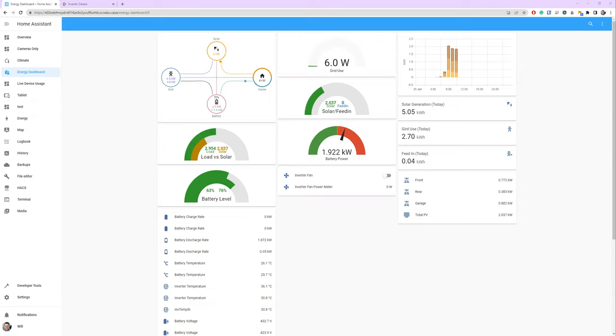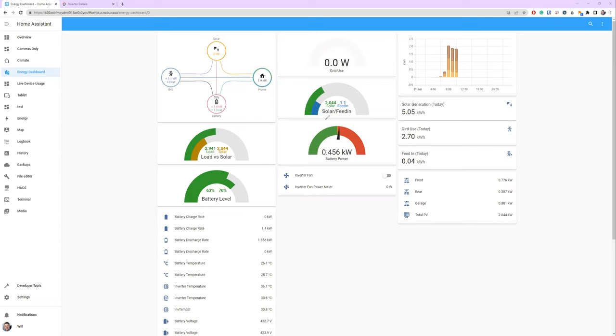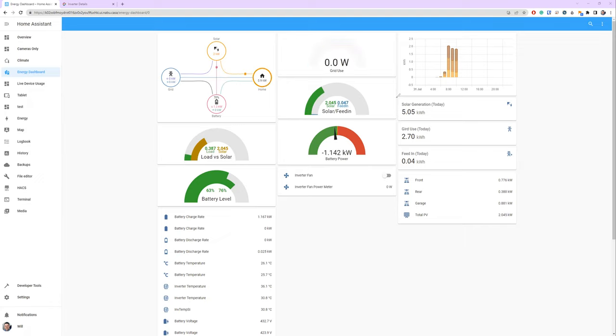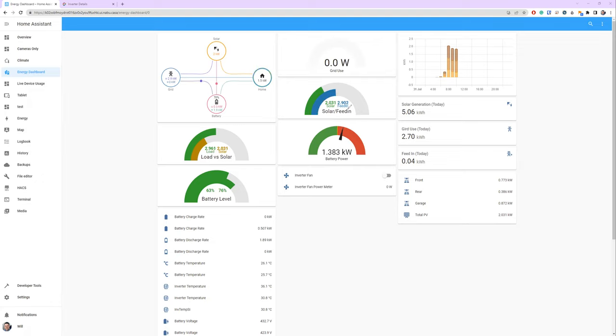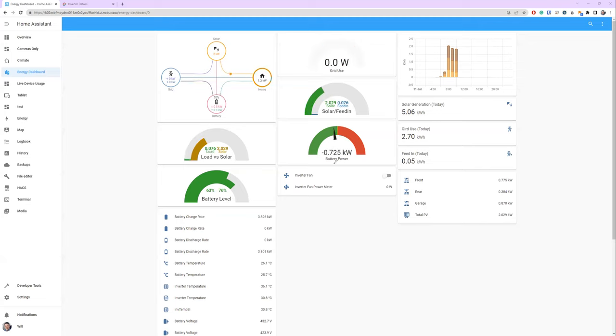So now we'll try turning the water heater off and we're going to watch in particular the feed-in amount here. So water heater is off. See, the feed-in jumps up and now the battery's responding. The grid has gone wild. This is the problem with any battery-connected hybrid inverter that's grid-tied. I'll add the load again. Water heater's on. Batteries responding, got a bit of feed-in going on right now, and now it's balanced out.